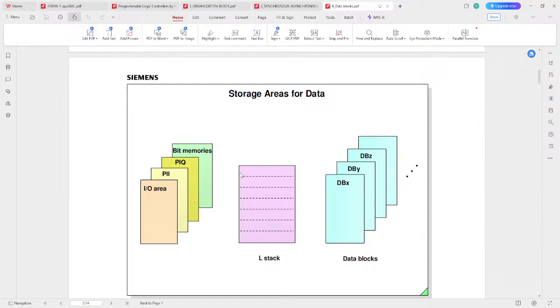So you are giving M0.0 to like M24.0, even more for you said. But you are giving yourself space, so you have liberty to use as much as you want, but you ensure you are separating them. Anytime I want to do double word, I start from like 60, MD60, so that I'm sure that I've not used it for bit or byte or word. So I give it space.